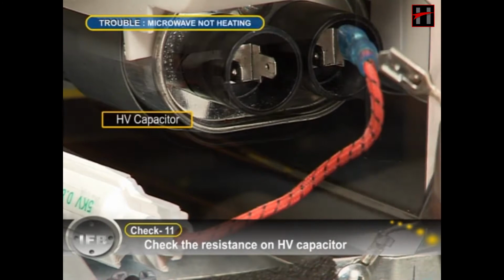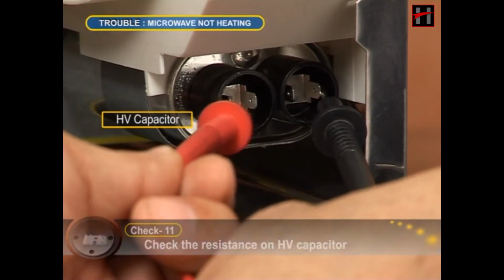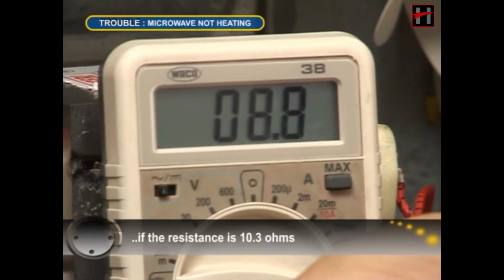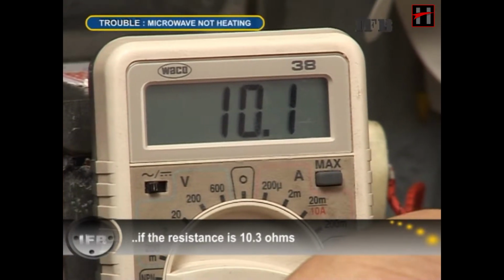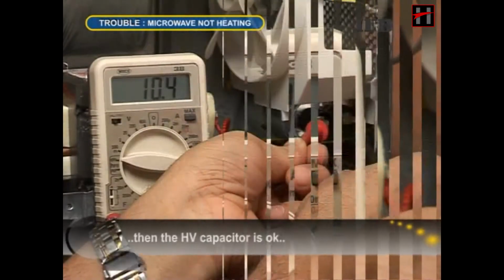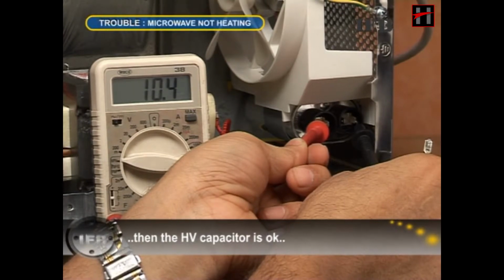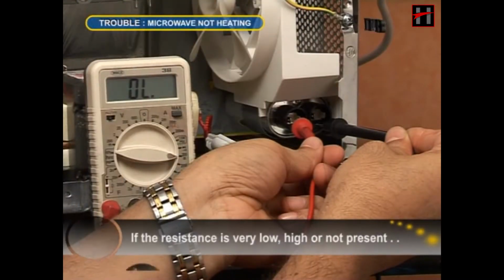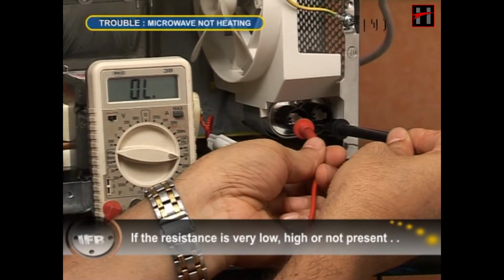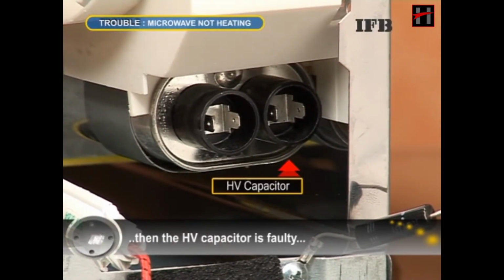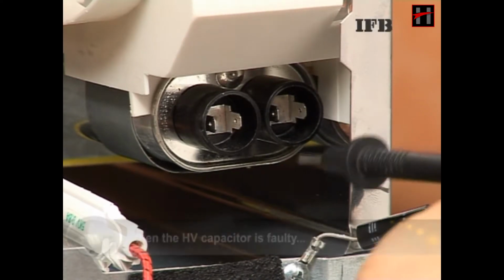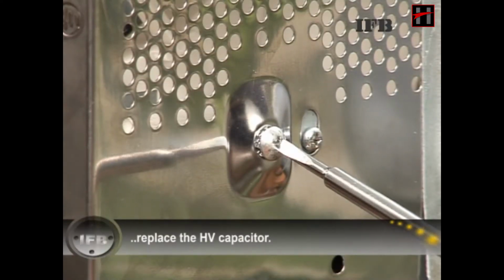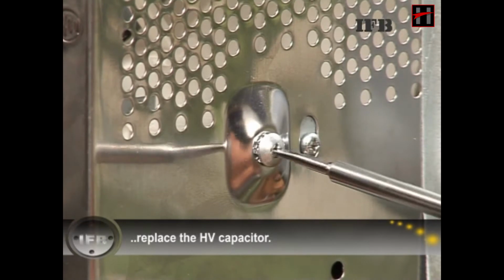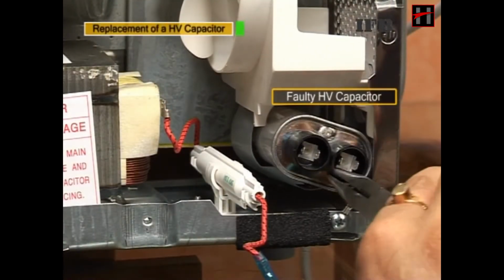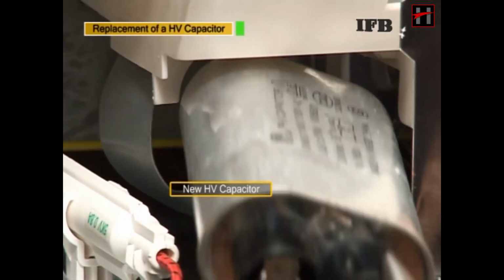Check the resistance on the HV capacitor. If the resistance is 10.3 mega ohms, then the HV capacitor is okay. But if the resistance is very low, high, or if the resistance is not present at all, then the HV capacitor is faulty. Replace the HV capacitor and put a new capacitor.